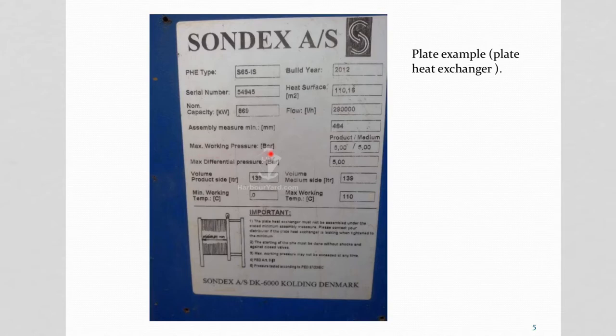Then you've got indications like max working pressure. You don't want to put too much pressure in a plate exchanger, because you see the design is made of plates that are stuck against each other and separated by gaskets. Too much pressure will generate leaks and all sorts of issues. So it also indicates what the volume of fluid on one side, here called the product side, and on the other side is. Here you've got the whole volume that is trapped into the heat exchanger. Here is like 139 liters, for example.